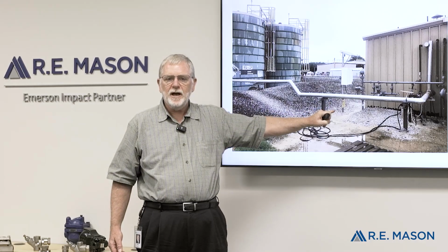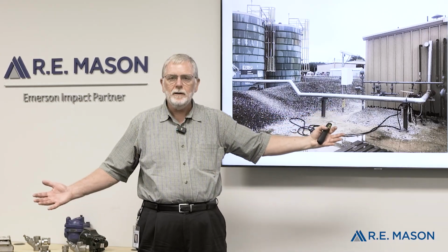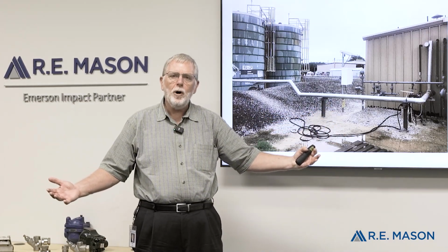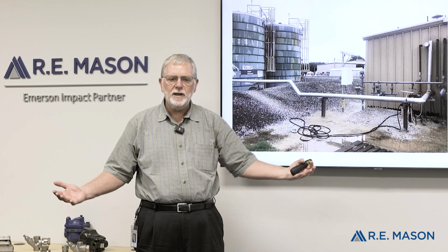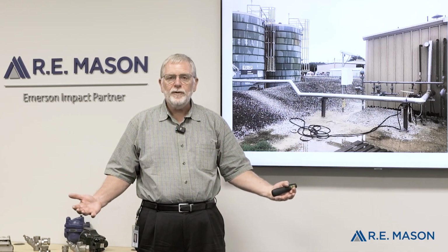When your system shuts down and starts up, there's no way of draining it. So when you go to start up, all of a sudden you've got your steam on, you've got to do something with that condensate. You're going to end up with a water hammer, you're going to destroy piping, you're going to be looking at things like that. So here's an area that we would show to you and recommend that we need to put a trap in to help improve your system process.